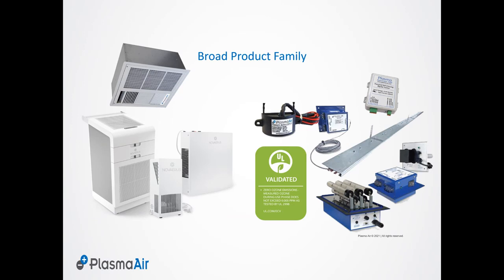So we've got the air purification products that are not only flexible in their installation, but when you look at installing the HVAC components, there's no pressure drop associated with them, none. There's low cost to operate them. Any of the bipolar ionizers is about the cost of a low energy UV lamp to operate. So there's no extra electrical requirements. So they're excellent for retrofit with the no pressure drop. There's no extra fan horsepower needed. And then again, with the first cost, it's also around the cost of what a low energy UV lamp is as well. So from a cost standpoint, very economical for the services that it provides.